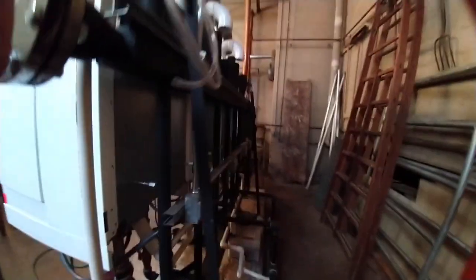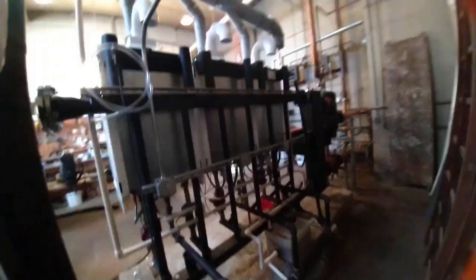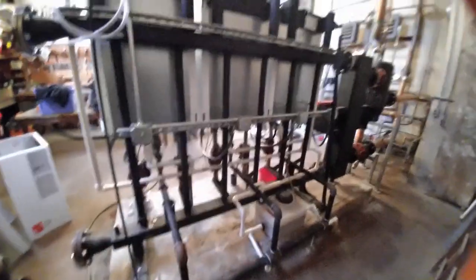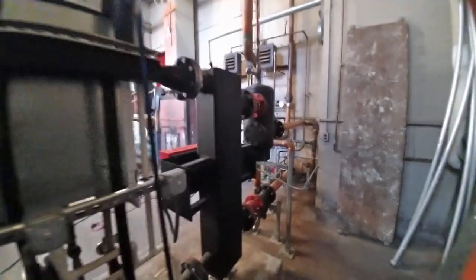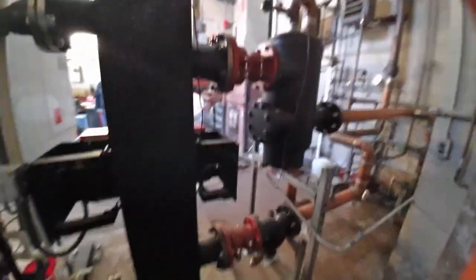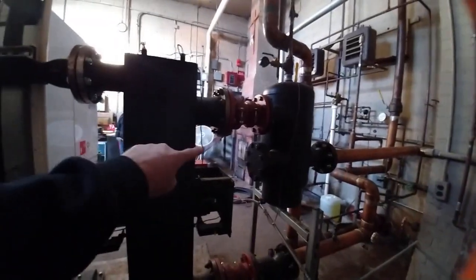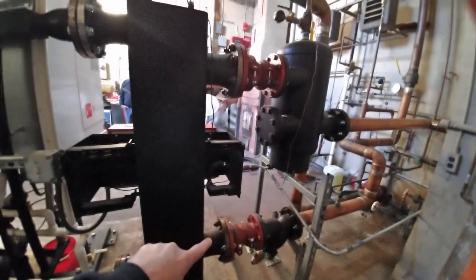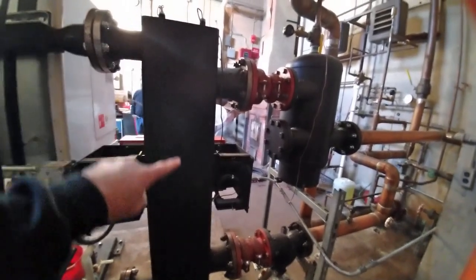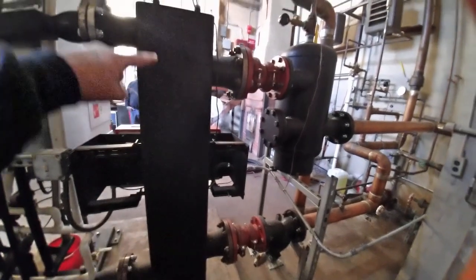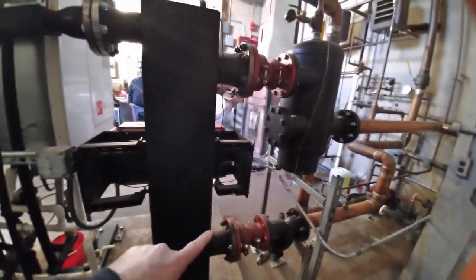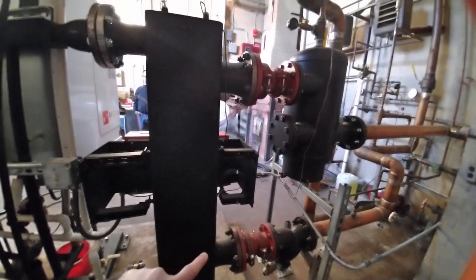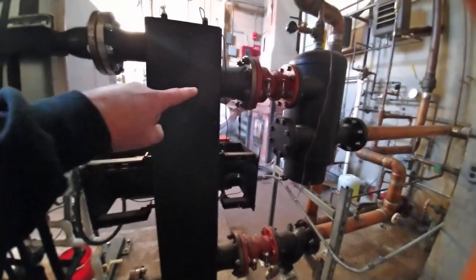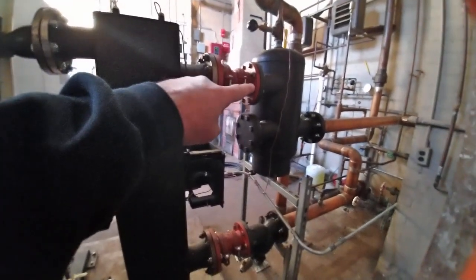Take a look at the back of the rack just to show how it's mounted. This rack is actually the water sections for this boiler. So the main circulator pump on this system pumps in and out of this, what Viessmann calls their low loss header. This is the hydraulic separator unit. We have return water from the system out in the building, coming back here. Supply water going out to the system goes this way. We have an air separator.